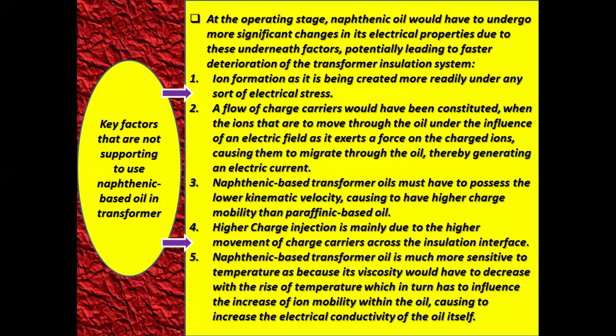Naphthenic based transformer oils possess a lower kinematic viscosity, causing higher charge mobility than paraffinic based oil. Higher charge injection is mainly due to the higher movement of charge carriers across the insulation interface.